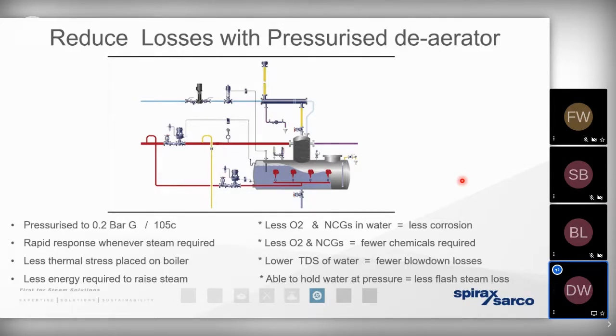But because of the pressure, we've purged off a lot of the non-condensable gases and a lot of the oxygen, which typically causes corrosion. Because of that, we need to add fewer chemicals to the feed water. So there's a cost saving there. And because we're adding fewer chemicals to the feed water, we need to perform less of that blowdown. It also means that because we're holding that water under pressure, we can recover more of the flash steam. It doesn't necessarily need to be vented away to atmosphere. So a pressurized deaerator can address a number of challenges that large steam using sites have.